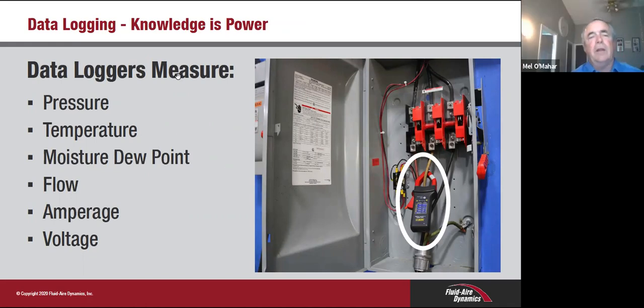Yeah, data logging, I'm very big on it. I feel it's very important. It can give you a picture of what is happening in your system. You can data log several points. You can measure flow, pressure, dew point, temperatures, amperage, voltage. And some of them are used to size a system. Some of them are used to troubleshoot a system.